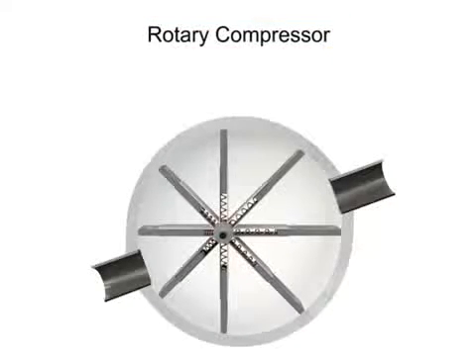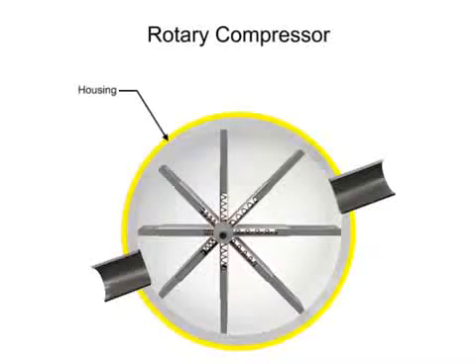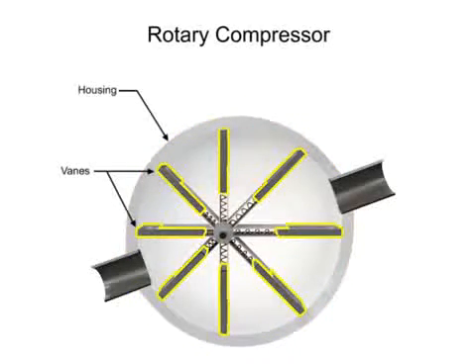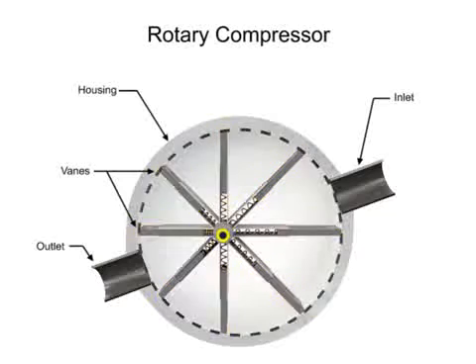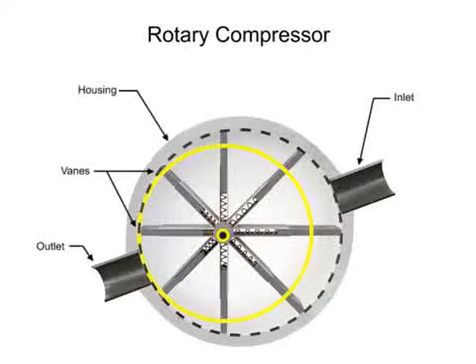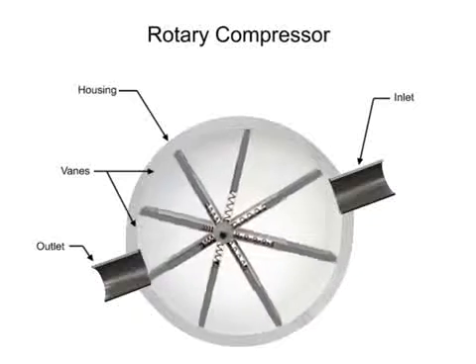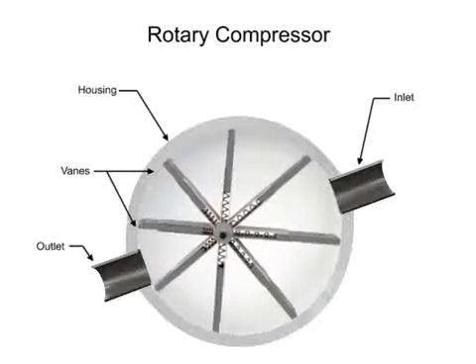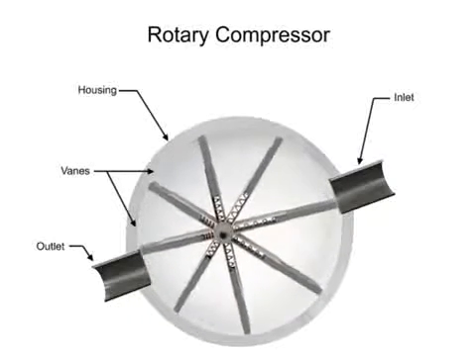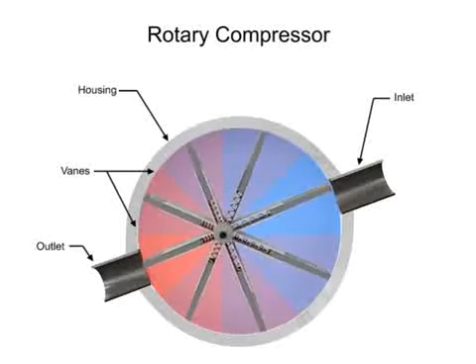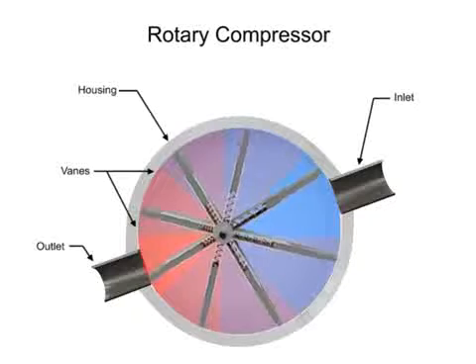Rotary compressors typically consist of a cylindrical housing with adjustable rotary vanes, an inlet, and an outlet. The vanes are on an off-center drive shaft. As the shaft rotates, the vanes slide in and out to maintain contact with the cylindrical compressor wall, creating chambers within the cylinder of varying sizes.